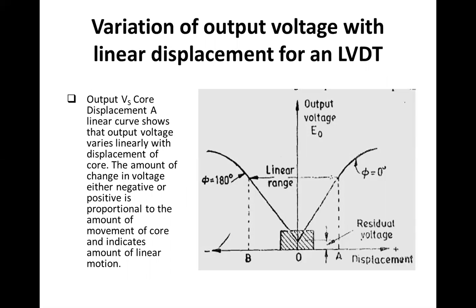This is the variation of output voltage with linear displacement of an LVDT. From the curve, you can see that the output versus core displacement is a linear curve, which shows that output voltage varies linearly with displacement of core. The amount of change in voltage, either negative or positive, is proportional to the amount of movement of core and indicates amount of linear motion.